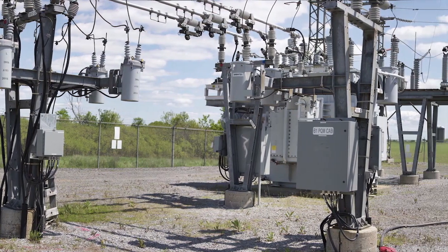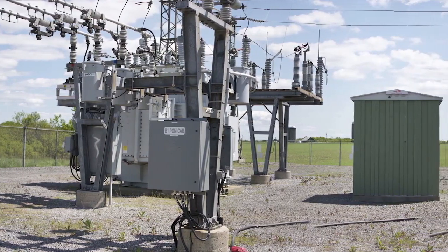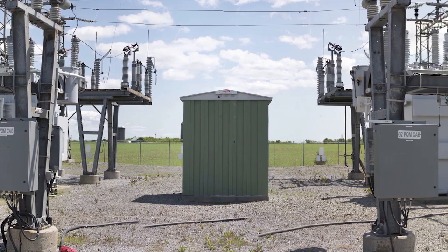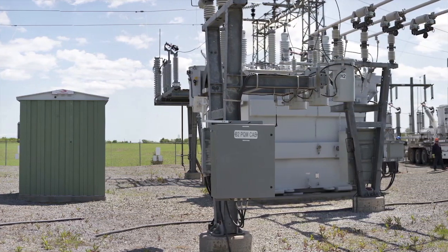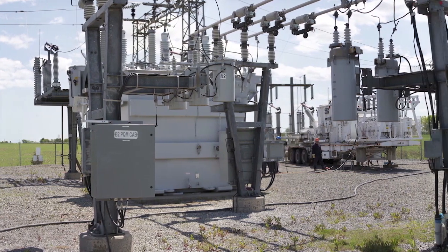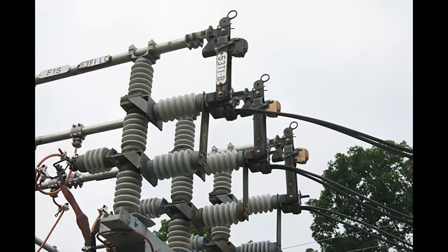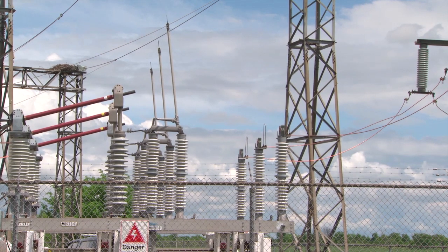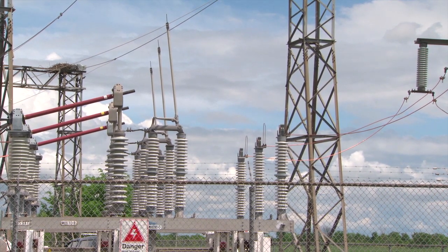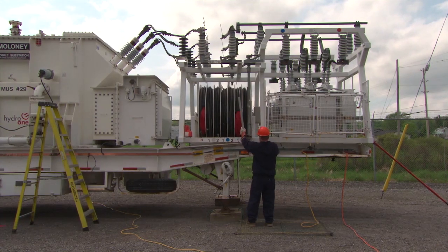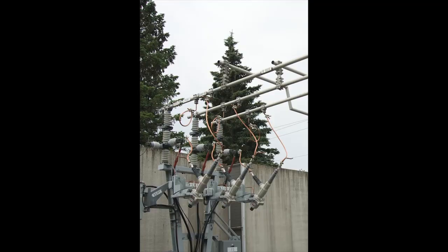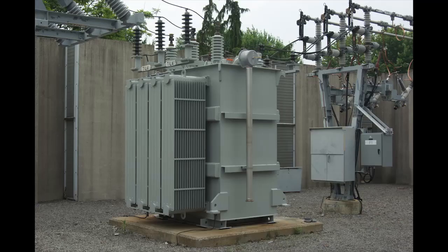A U70 station, sometimes referred to as a low-profile station, is built lower to the ground for aesthetic reasons. The supply voltage can enter the station either overhead or underground. The feeder supply exits the station underground and connects outside the station on pole structures equipped with dip switches. These stations are equipped with a T-B switch that isolates the transformer from the low-voltage bus. The MUS high-voltage connection taps into the high-voltage termination and mobile connection structure. The MUS low-voltage connection typically taps into the low-voltage bus supplying the outgoing feeders that form the station egress. The MUS in this case isolates and allows de-energizing of the station transformer, but not the low-voltage bus.